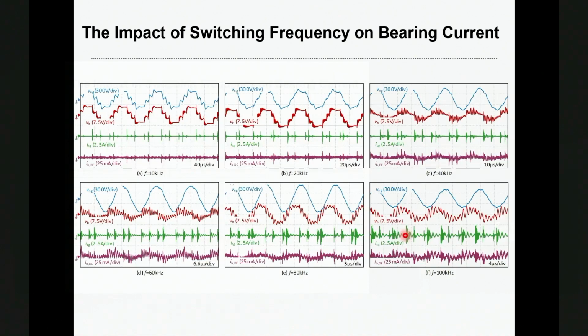And we have tested the bearing current under switching frequencies from 10 kilohertz to 100 kilohertz. As you can see, under 10 kilohertz, most waveforms look as predicted, where there are 4 voltage levels in the common mode voltage, or the neutral to ground voltage. But this has turned into more sinusoidal-like waveforms, and there will also be more oscillations in the bearing voltage and the bearing current.